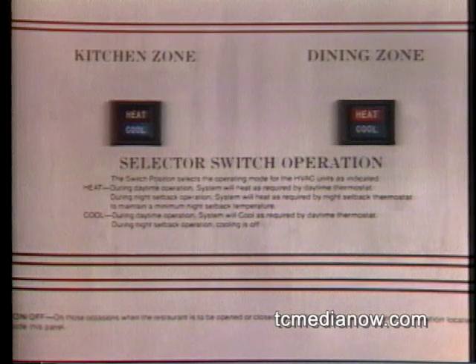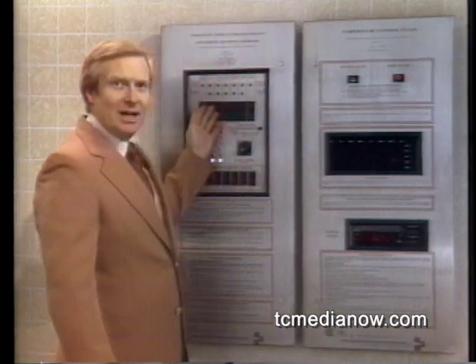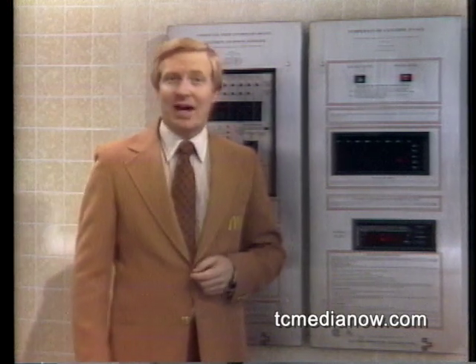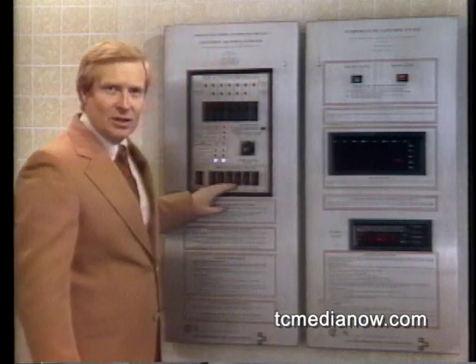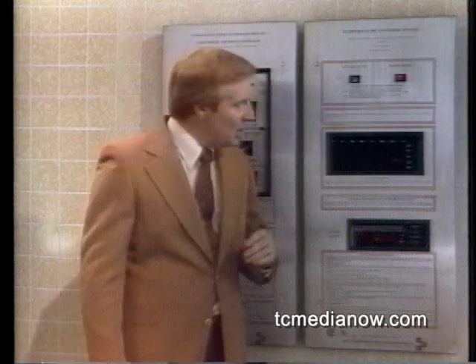The system divides the store into 2 zones: the kitchen and dining areas. These zones may be independently heated or cooled. When neither heating nor cooling is required, vent-only operation is automatically provided. The system control panel provides a number of status and diagnostic lights which make it easy to detect trouble conditions if they should occur and to take corrective action. In addition, the system provides a timing circuit for the store's exterior lighting. The heart of the system is this clock, which turns each system function on or off according to a schedule selected by the store manager and programmed into the clock.